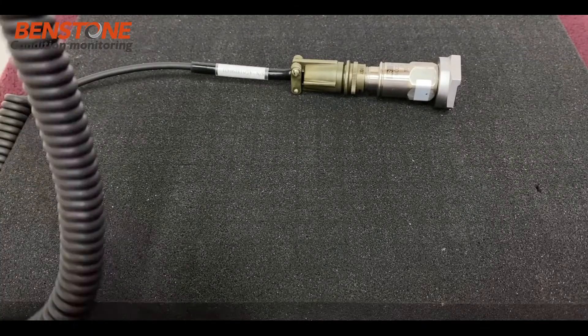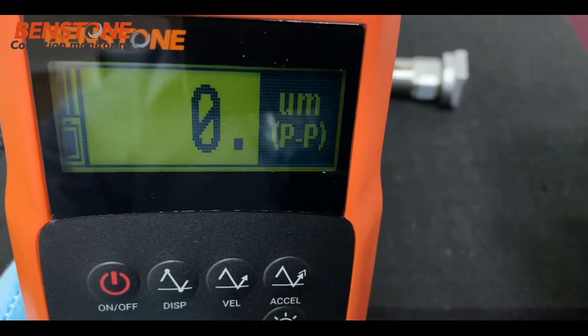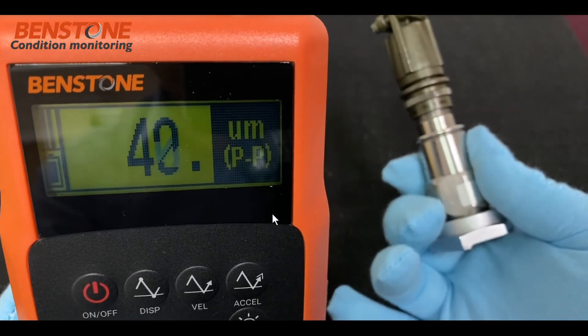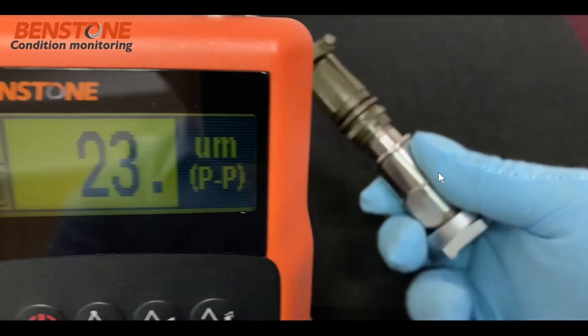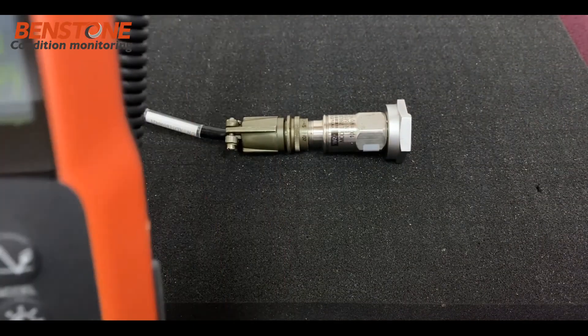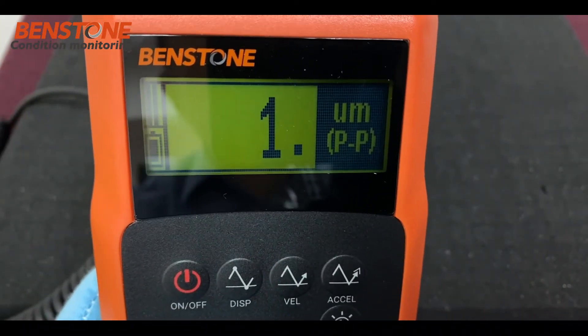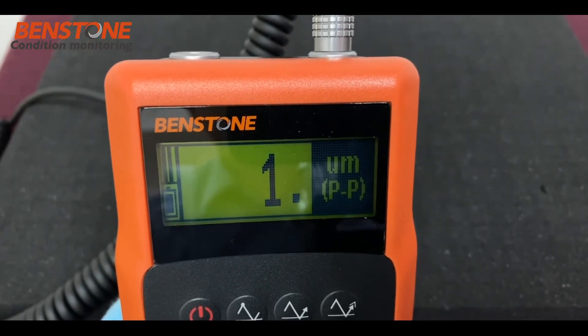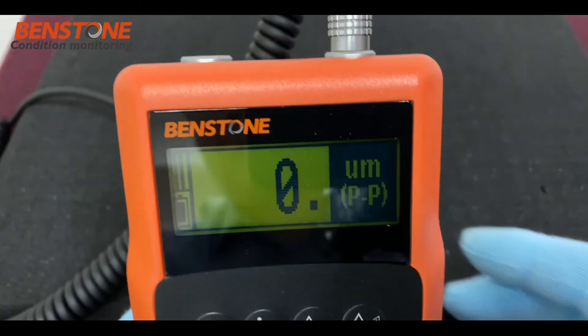In this video we will talk about the VPod meter and the quietness of the meter itself. We have a high quality accelerometer connected via cable to the VPod Light. As we place the sensor on the foam, you'll notice it will be quiet and the values will slowly go down to a very quiet isolated value. With a noisy or less capable meter you would see the number bounce around, but in this case — set at microns peak-to-peak — it settles down to zero.